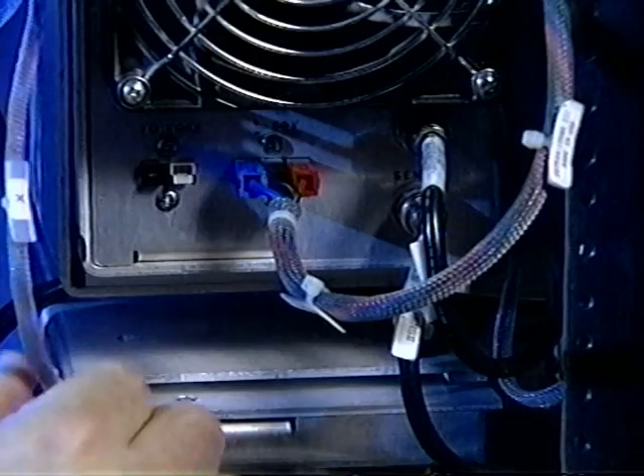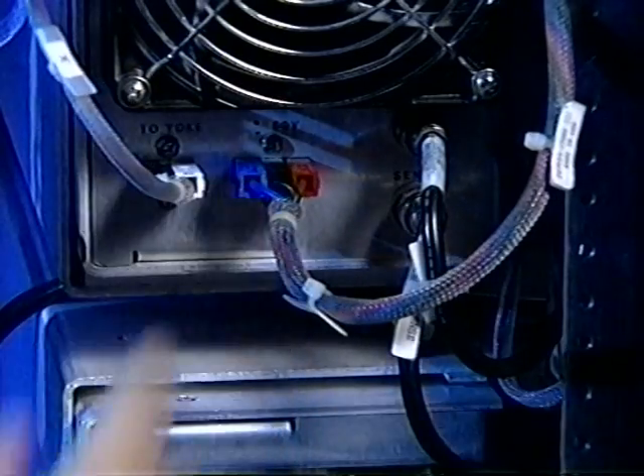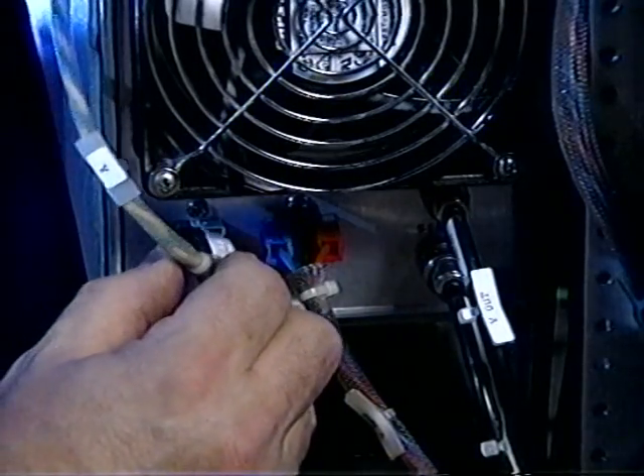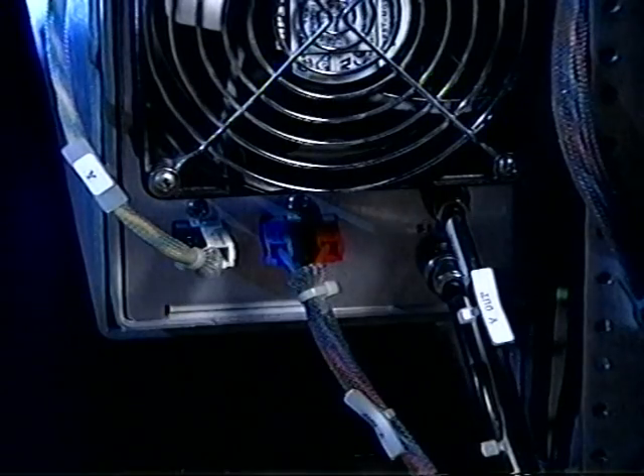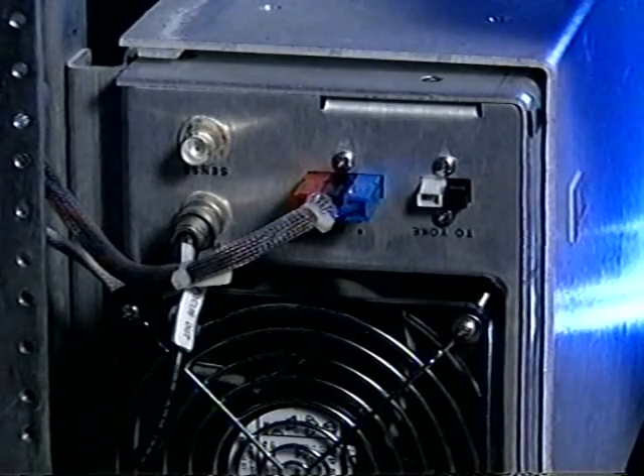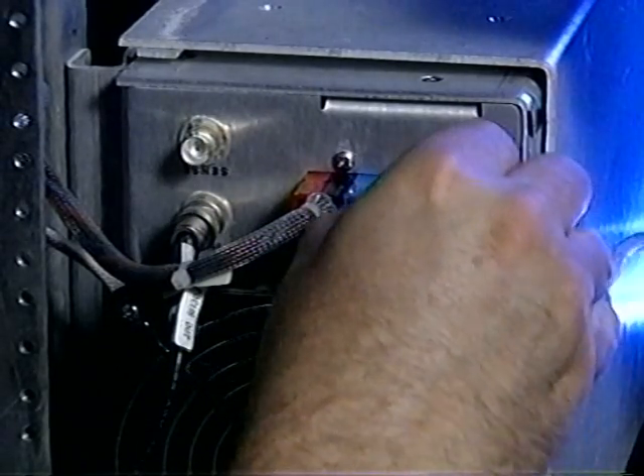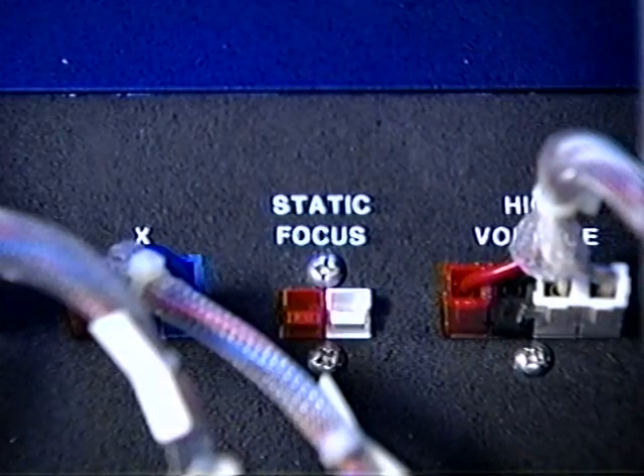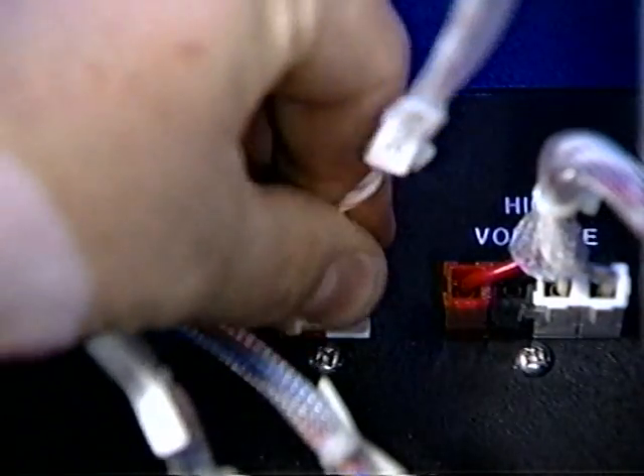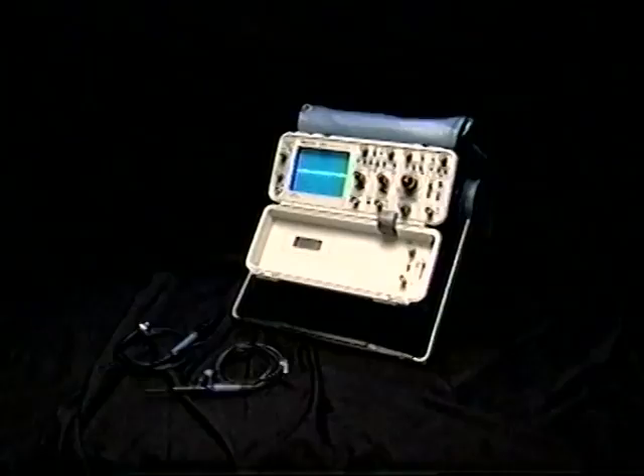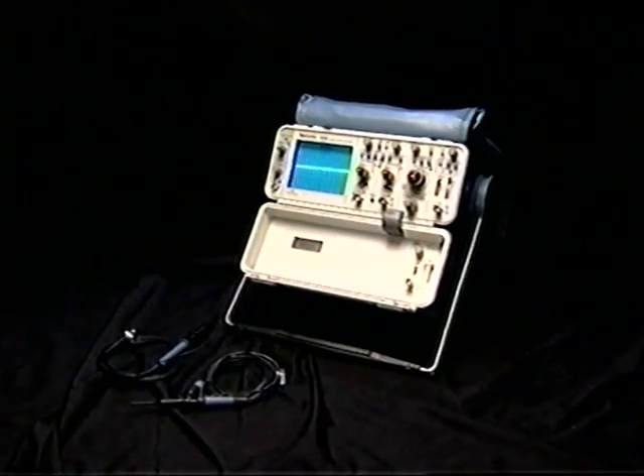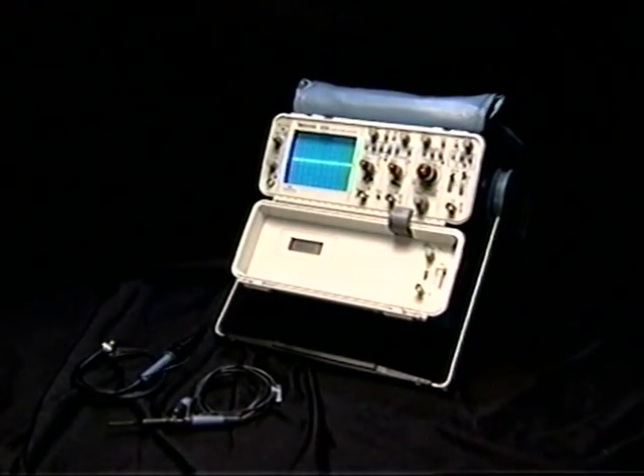Connect the DC power cable and yoke lead to the X amplifier. Connect the DC power cable and yoke lead to the Y amplifier. Connect the DC power cable and coil lead to the focus amplifier. Connect the static focus cable to the rear power drawer connector labeled static focus. Proper setup requires an oscilloscope to monitor a test point on the video card.